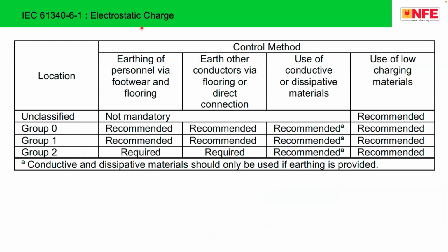Similarly, electrostatic charge. Electrostatic charge can accumulate by friction of various parts, probably the dress of the medical practitioner or the medical staff. If the charge is discharged to the equipment or to the patient's body, this is fatal. The IS standards recommend electrostatic charge controls such as earthing of personnel via footwear and flooring, and earth conductors in flooring or direct connection. So different methods are recommended, and in Group 2 locations they are required. In Group 1 locations there are some recommendations. So ideally these measures are to be implemented.